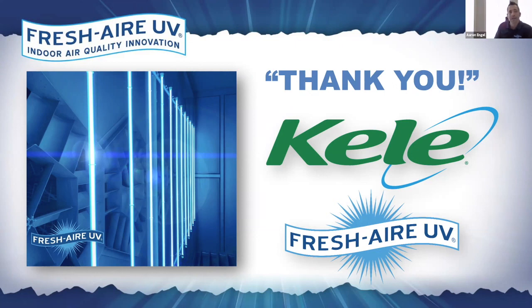Case in point, you saw that example of that one coil with a single lamp, and that would be perfectly fine for coil disinfection. But that single lamp in a 48 inch by 40 inch high coil will certainly not be powerful enough for air disinfection. So you would need four times the amount of lamp. That's part of the benefit of the calculation software that we have: when you get a report, you will see in real time what the power will be for inactivating that particular scenario.